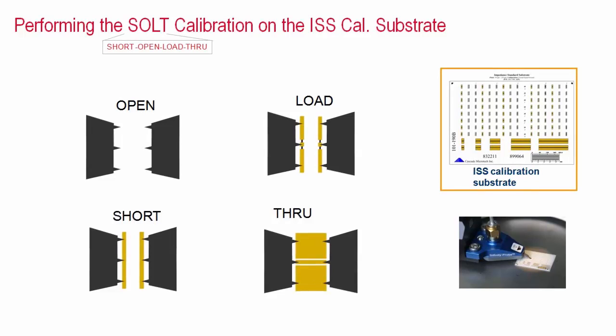For the SOLT, short open load through calibration shown here, the cal standards are successively connected and measured. Once the calibration is done, it is saved in the network analyzer to later provide corrected calibrated device measurements.